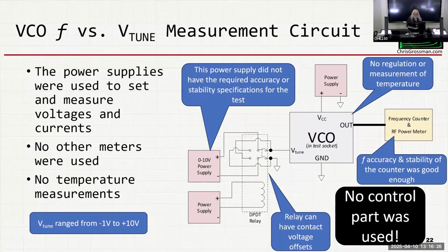I looked at the accuracy of the meters. The specified accuracy on the power supply really wasn't good enough for this test. They never even looked at that. As I had talked about before, when a relay switches, you can get different contact voltages, and those can change when it switches.